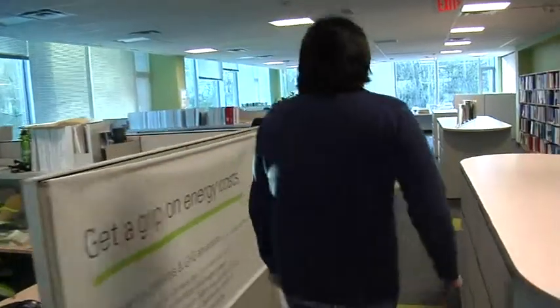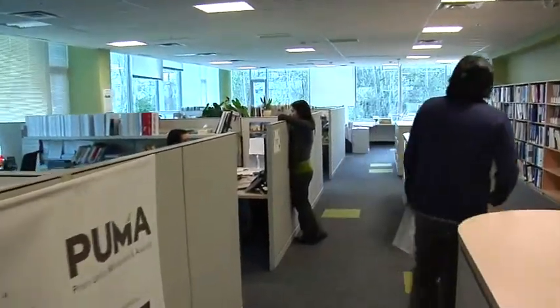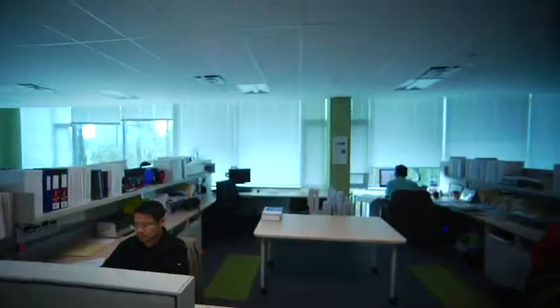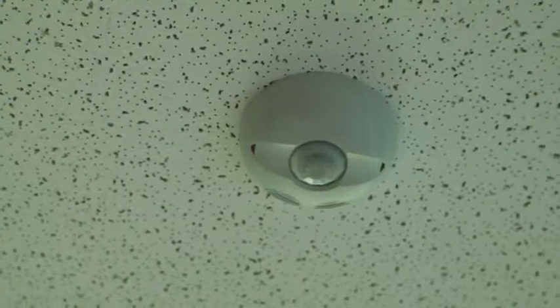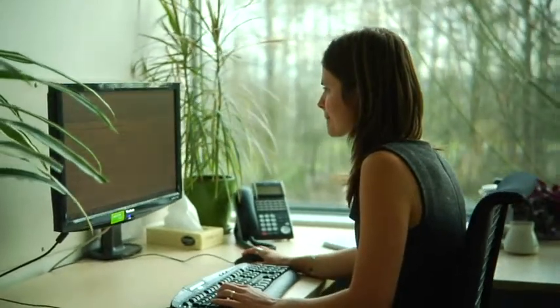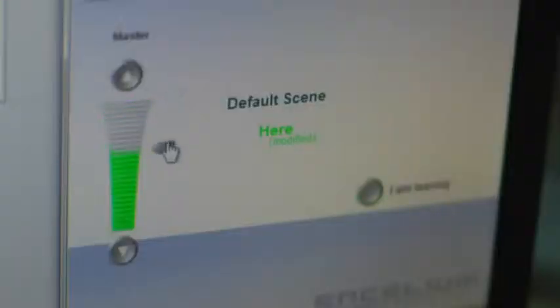We've gone away from having the automated lighting control system turn the lighting on and we've turned it into a manual mode. When the first person comes in in the morning, they will turn on the lighting in the common areas only — this allows people to get to their workstation safely. Once they enter into their work pods, an occupancy sensor will kick in the lighting for that pod area only. Once at their workstations, they've got computerized access to the lighting systems above them, so they can increase the light level or even turn it off if they so desire.